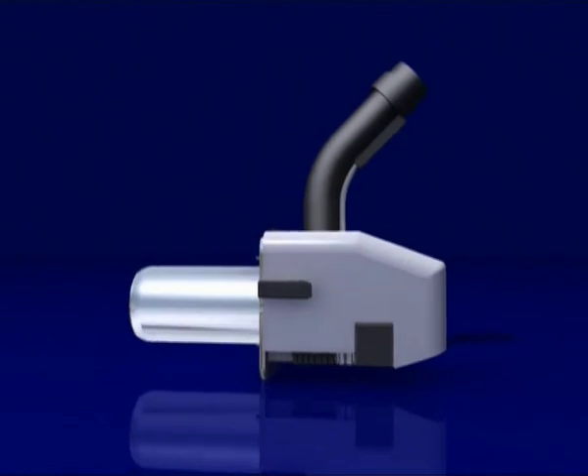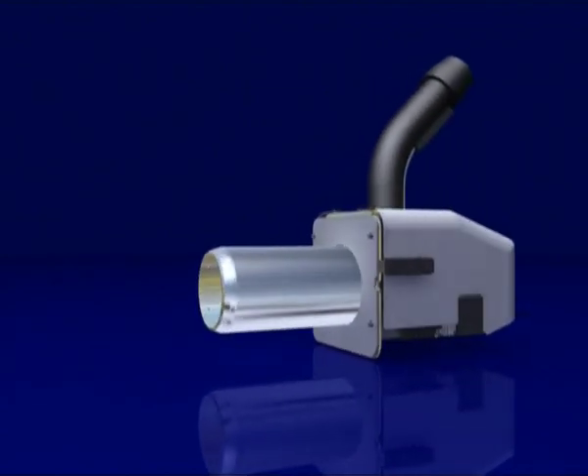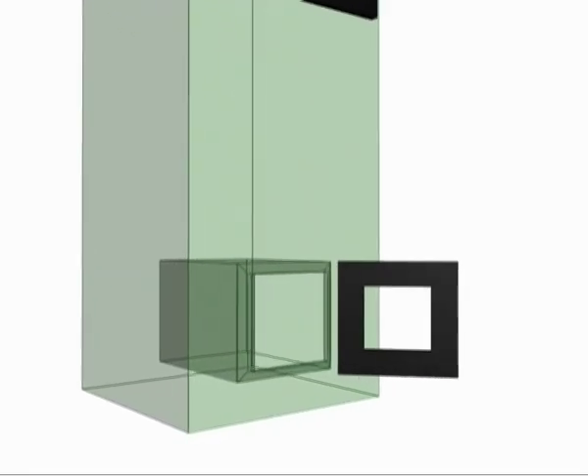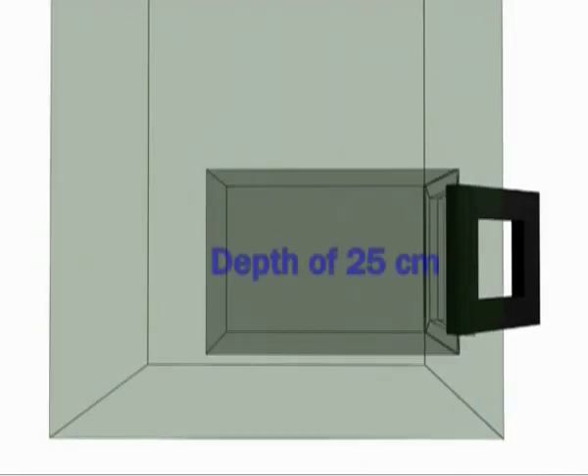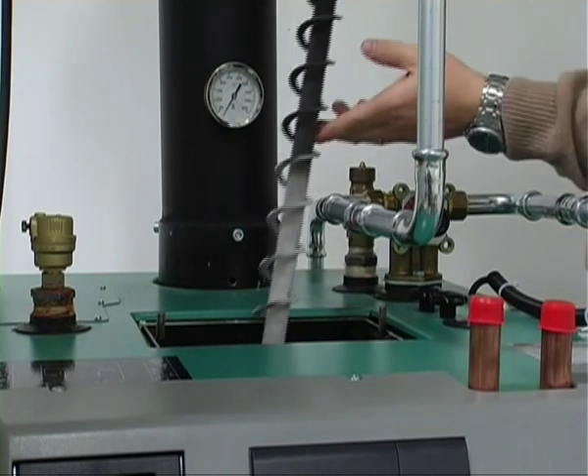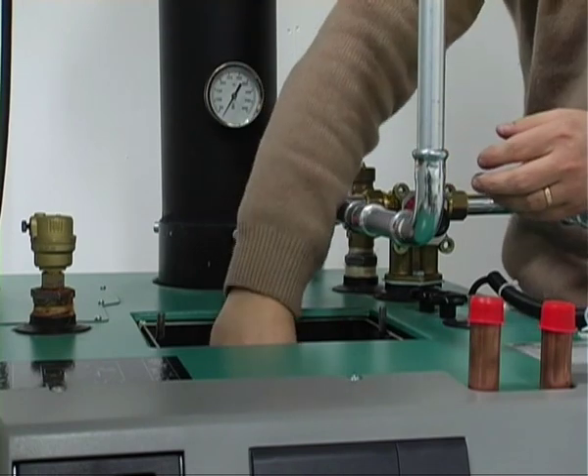The Viking BO is a modern and efficient pellets burner for private housing. The burner flares forwards, which means it's suitable for most boilers. It requires an opening not less than 13 by 13 cm in size and a firebox with a depth of 25 cm. As the Viking BO has the unique ability to withstand high counterpressure in the firebox, the turbulators can be left in place in modern boilers, so the heat is put to good use in the boiler instead of being lost out the chimney.